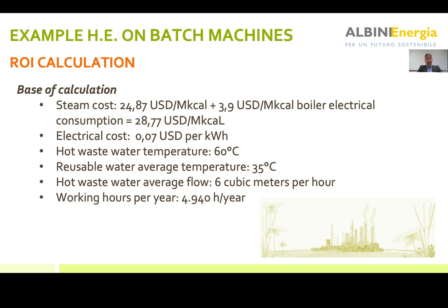This slide shows the return on investment calculation. We started from the steam cost that the company was paying, which was around 25 US dollars per megacalorie, and then we had 3.9 US dollars per megacalorie which is more related to the pump consumption of the thermal oil.